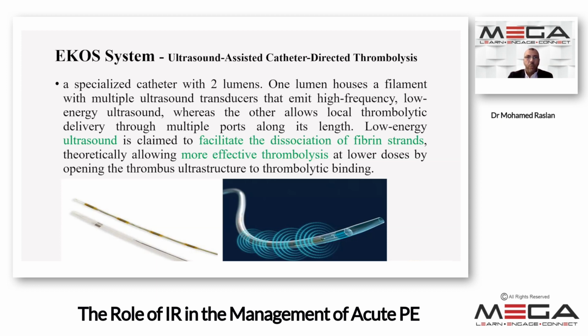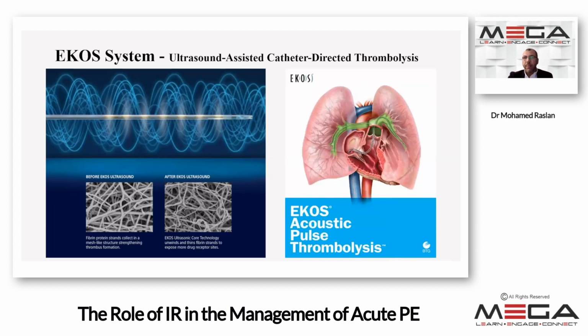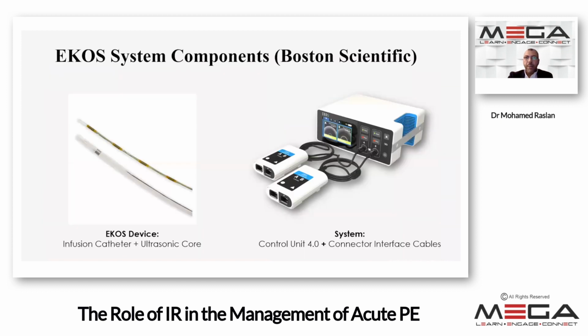Low energy ultrasound is claimed to facilitate the dissociation of fibrin strands, theoretically allowing more efficient thrombolysis at a lower dose by opening thrombus ultrastructure to thrombolytic binding. As you can see here, these are the ultrasound probes running through the catheter. So it's claimed that EKOS ultrasound helps to unwind and thin the fibrin strands to expose more drug receptor sites. In other words, it opens thrombus ultrastructure to thrombolytic binding, as you can see here in the demonstration image. And this is how the latest model of EKOS looks.